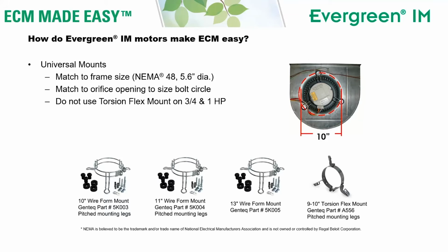When a mount is rated for 11 inches, that's the diameter of the bolt circle. So to get my bolt holes on the sheet metal on a blower that has an air opening of 10 inches, I would need at least an 11-inch mount. And we make mounts from 10, 11, and 13-inch bolt hole diameters.